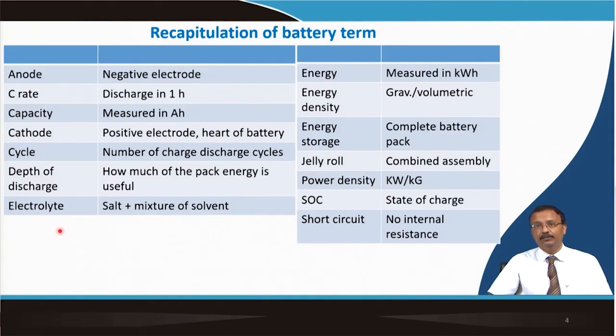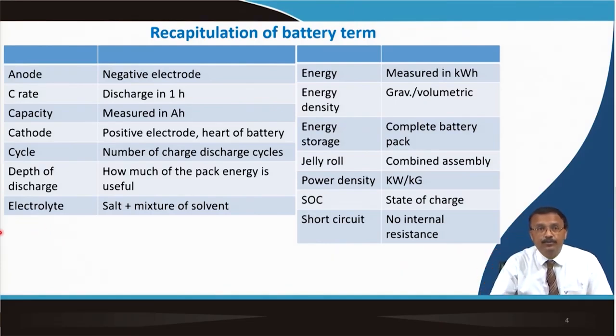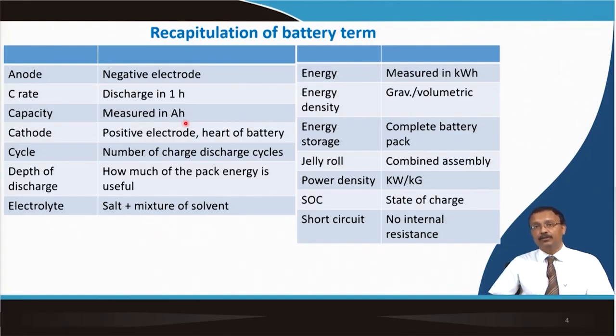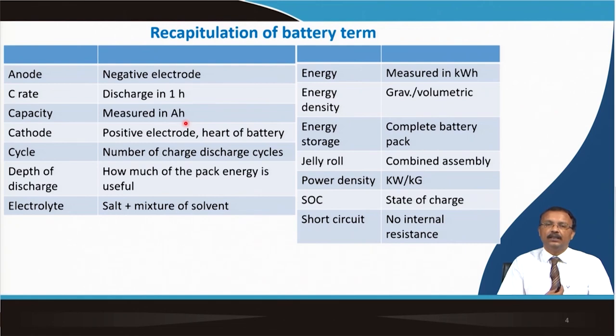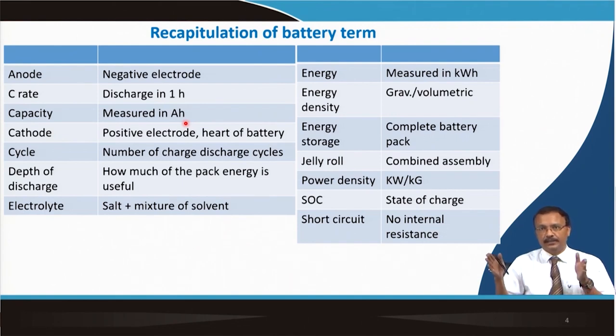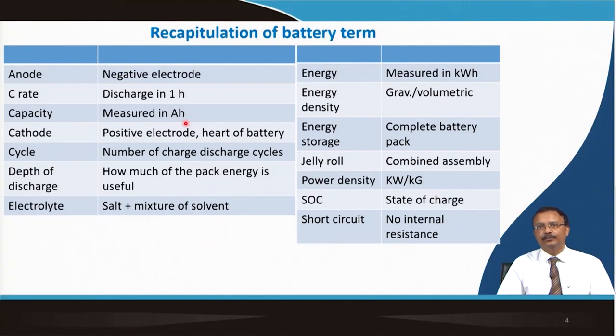If you discharge it in one hour, you are discharging at 1C. Capacity is usually measured in ampere-hours during discharge: you drain a constant current and measure the fall in voltage, because voltage changes as lithium ions are inserted into the positive electrode material during discharge. The voltage continuously falls, and by knowing the current and time, you calculate the charge stored — that is the capacity in ampere-hours.